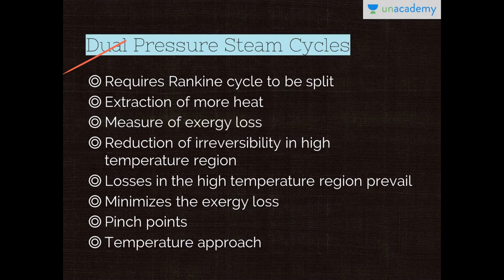Moving on to dual pressure steam cycles. The Rankine cycle is required to be split in order to decrease the irreversibility involved in the heat transfer between the hot exhaust gas and the water or steam. The next figure shows a diagram indicating the heat flow from the flue gas to the water-steam cycle. It can also be seen that more heat can be extracted from the exhaust gas if the steam pressure is lower. The temperature ratio T0/T is actually a function of Q. At high steam pressure, the temperature difference or irreversibility is reduced in the high temperature region and the losses are dominant in the lower temperature region.